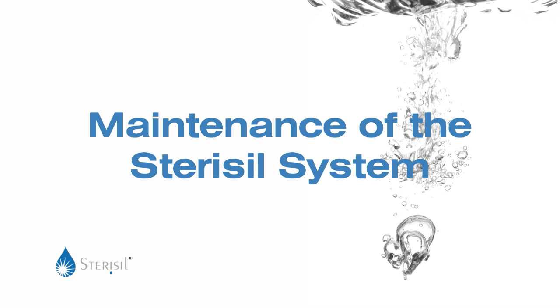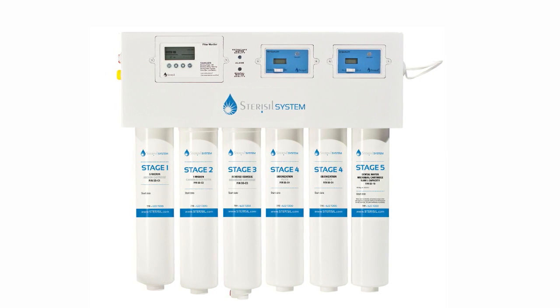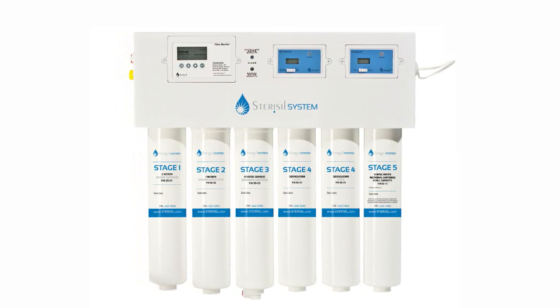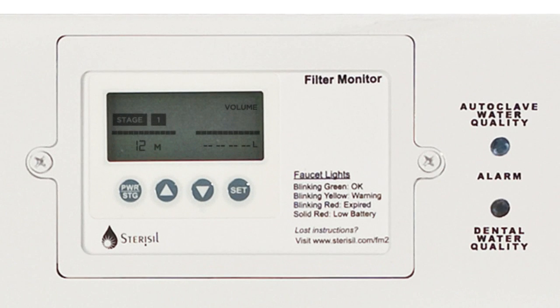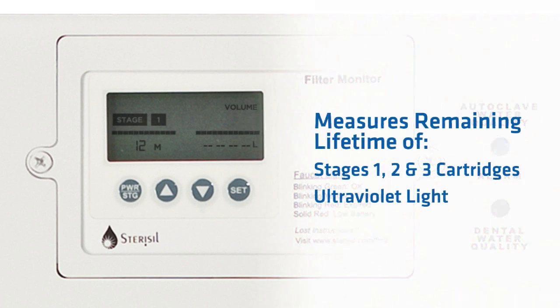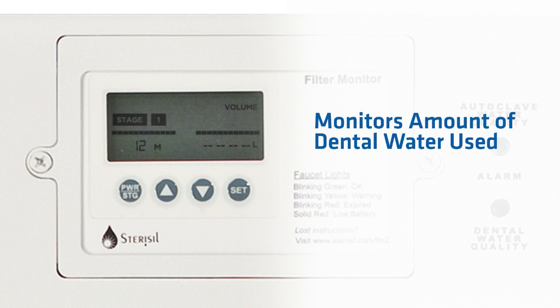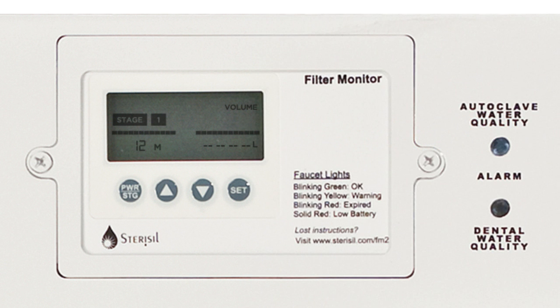This section will go into more detail on the monitors and then take a closer look at the stages of the Sterisil system to better understand how to troubleshoot and maintain the system. The white filter monitor is used to measure the remaining lifetime of stages 1, 2, and 3 and the UV light. It will also monitor how much dental water has been used to date.